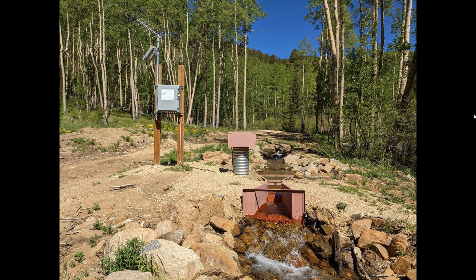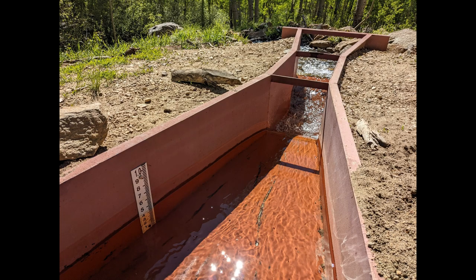This is a picture that I took in a much nicer environment than a wastewater treatment plant. It's a Parshall flume, and I was so excited to see it out in the middle of nowhere that I took about a million pictures of it, and these are just a couple. The way a Parshall flume works is that you measure the depth of flow at a certain known location, and then, assuming that the downstream water isn't affecting the depth at that location, it's relatively easy to calculate the flow rate as a function of how deep the water is. For a certain throat width and a certain approach angle and slope, there would be a pretty clear relationship between the depth of the water and the flow rate. And so that's the basis of a Parshall flume.